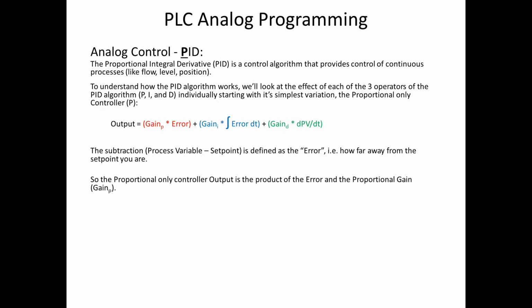PID control, rather than go into this, I will let you know that PID control stands for proportional, integral, and derivative. Proportional basically gives you a change based on the difference between what you want and what it is. That is the main type of control that the PLC usually uses. It's the one that should handle 90% of the control system.